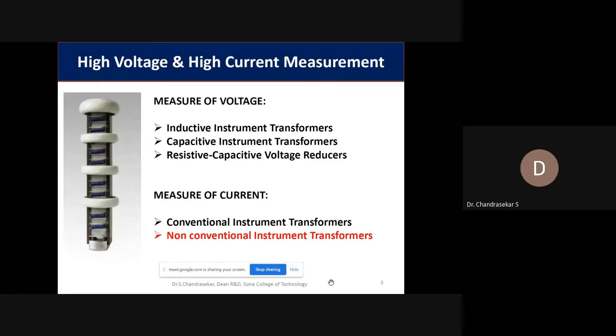Okay, in such big, huge devices like transformers or even in cables, we are using all these types of insulation: solid, liquid and gas. Even in Chennai, there is a completely gas insulated substation. In Mylapore, there is a completely SF6 gas insulated substation. This is mainly chosen for the dielectric strength of the medium. The gas insulated system has a very good dielectric strength, better insulation properties than solid and liquid. And liquid is mostly preferred in transformers because it has self-restoring capability, and we can also easily replace the liquid insulation.